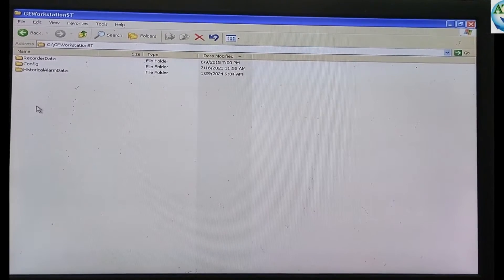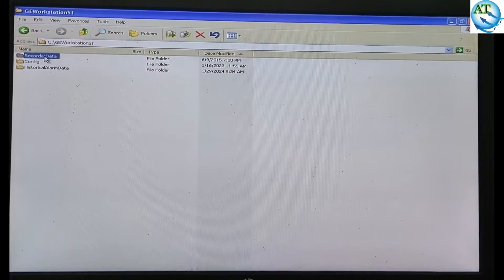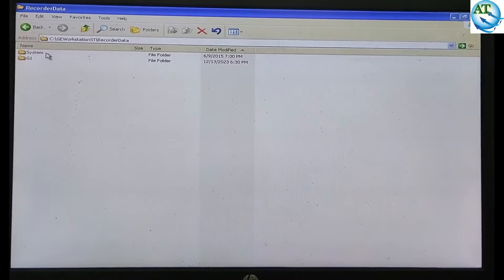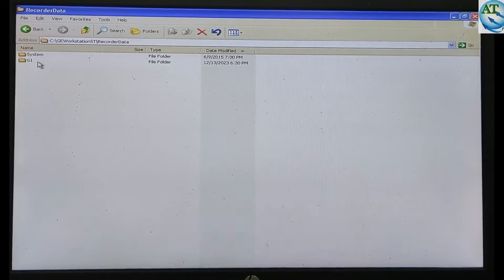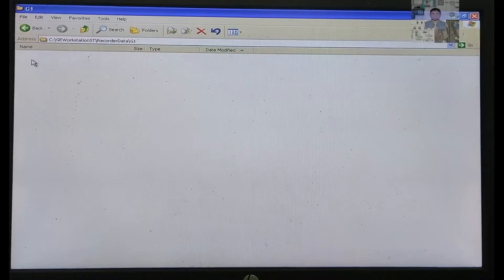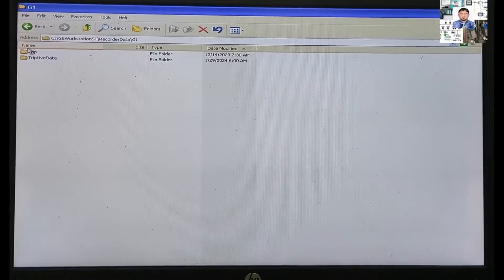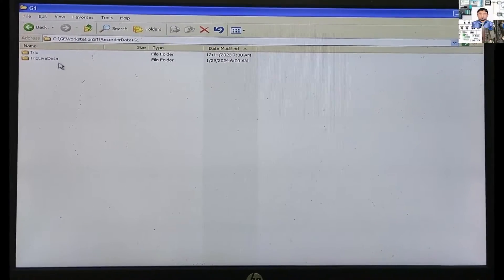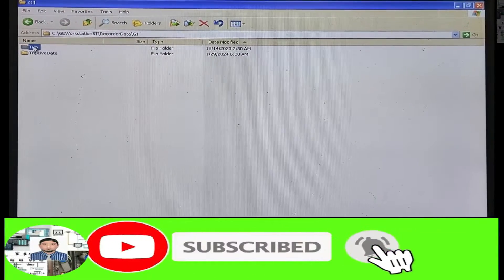Then go to the Recorder Data. In Recorder Data, you see System and G1. Go to G1. In G1, here you can see TRIP and TRIP Live Data — two types of folders are available here. TRIP Live Data is the running data, and TRIP is the recorded TRIP data.